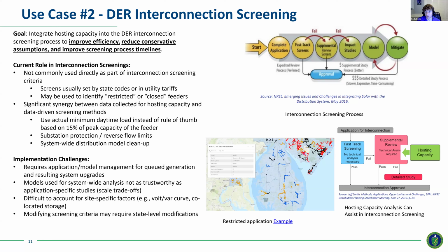It seems intuitive, but this hasn't been that commonly used. There's overlap in some of the underlying data, but hosting capacity changes basically every time a system gets added, so it's hard to keep current. But there are factors like minimum load - using actual minimum load data can be really impactful in the screenings rather than relying on ballpark level 15% minimum thresholds. You can also get substation reverse power information that's really relevant to the screenings and can reduce the amount of conservative assumptions going on.